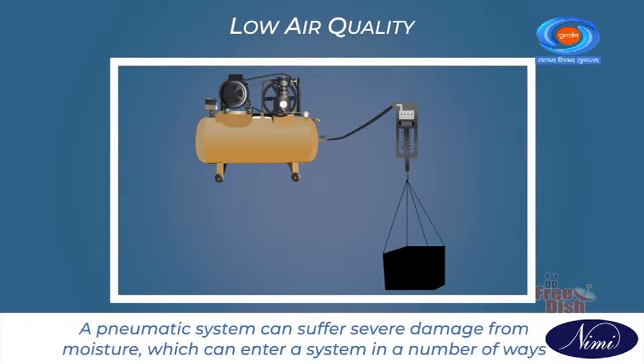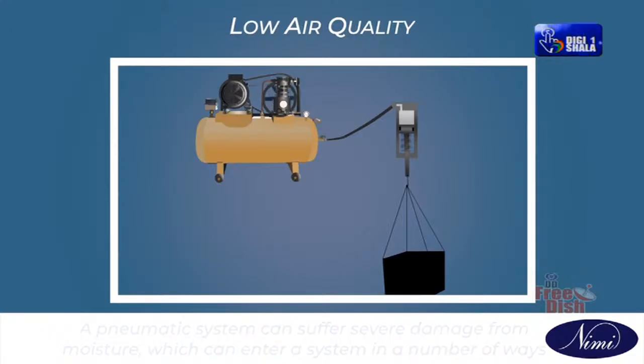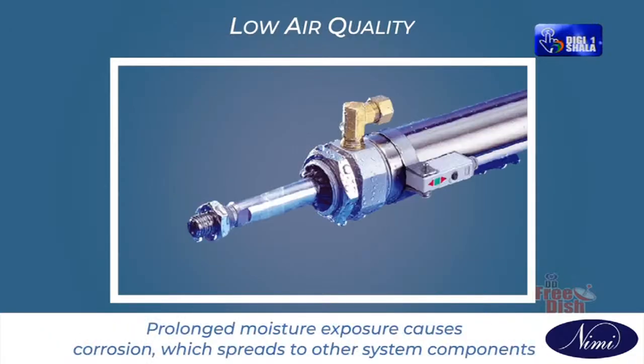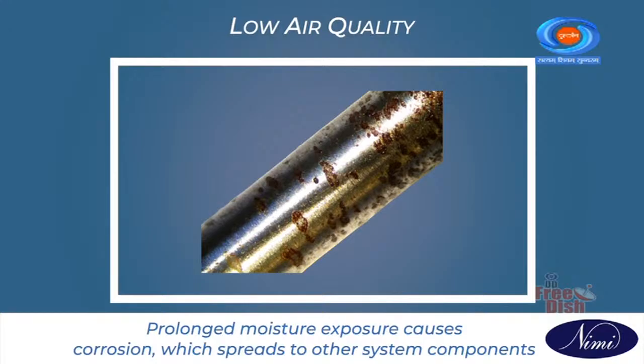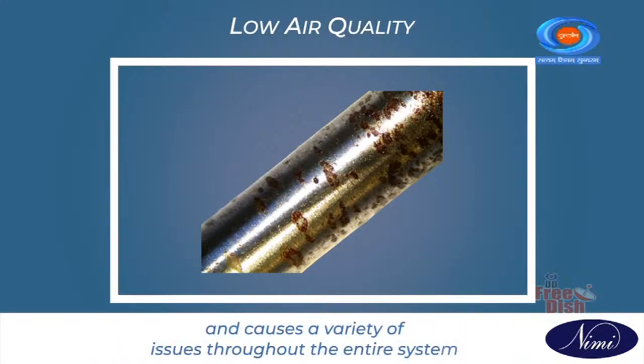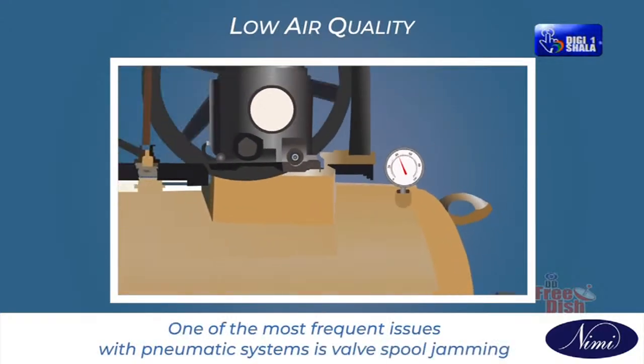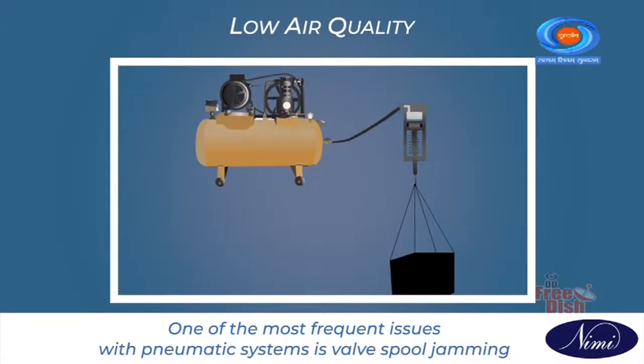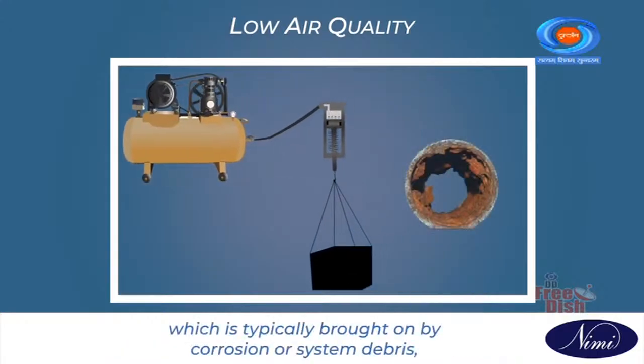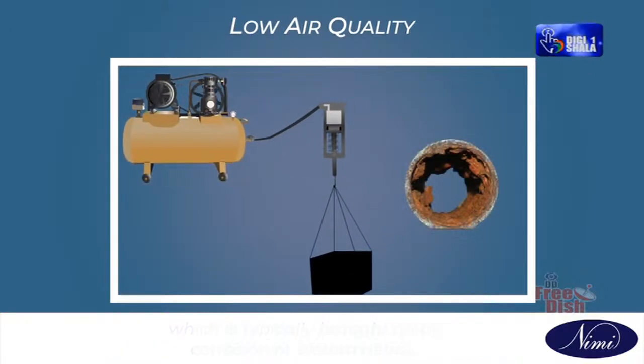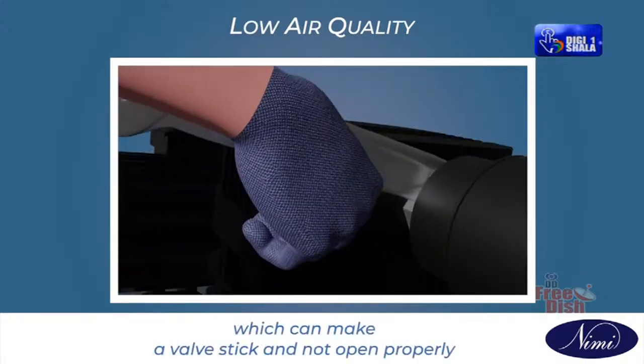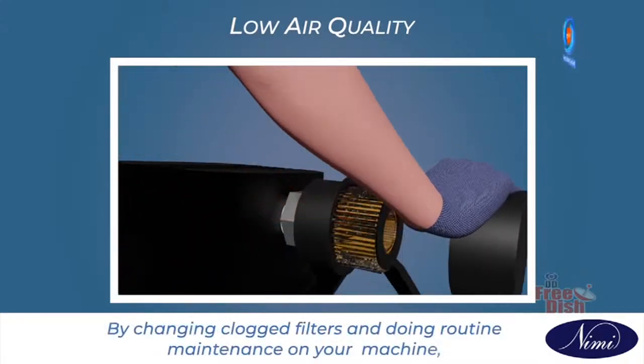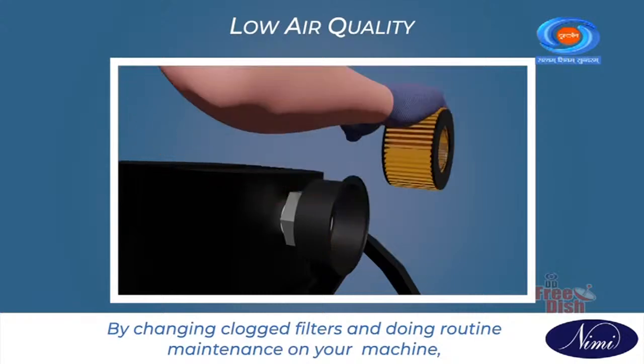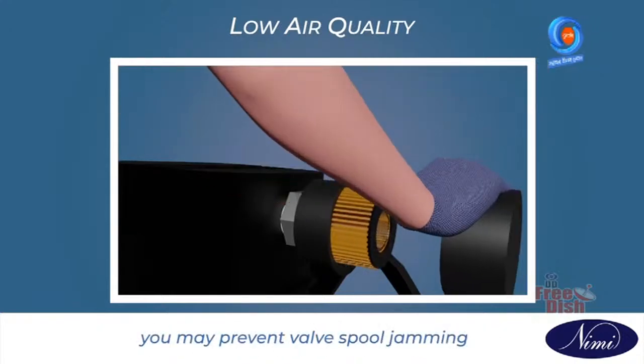A pneumatic system can suffer severe damage from moisture, which can enter a system in a number of ways. Prolonged moisture exposure causes corrosion, which spreads to the other system components and causes a variety of issues throughout the entire system. One of the most frequent issues with pneumatic systems is valve spool jamming, which is typically brought on by corrosion or system debris, which can make a valve stick and not open properly. By changing clogged filters and doing routine maintenance on your machine, you may prevent valve spool jamming.